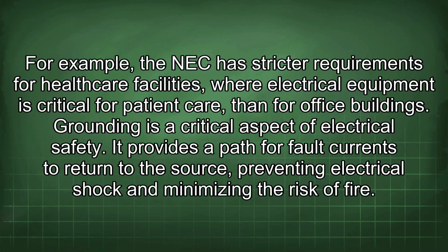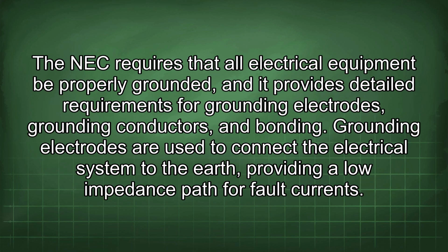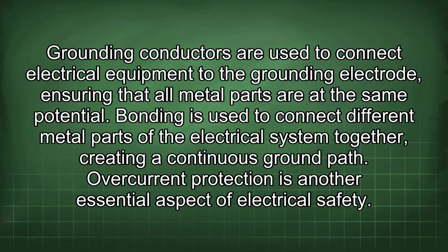Grounding is a critical aspect of electrical safety. It provides a path for fault currents to return to the source, preventing electrical shock and minimizing the risk of fire. The NEC requires that all electrical equipment be properly grounded, and it provides detailed requirements for grounding electrodes, grounding conductors, and bonding. Grounding electrodes are used to connect the electrical system to the earth, providing a low impedance path for fault currents. Grounding conductors are used to connect electrical equipment to the grounding electrode, ensuring that all metal parts are at the same potential. Bonding is used to connect different metal parts of the electrical system together, creating a continuous ground path.